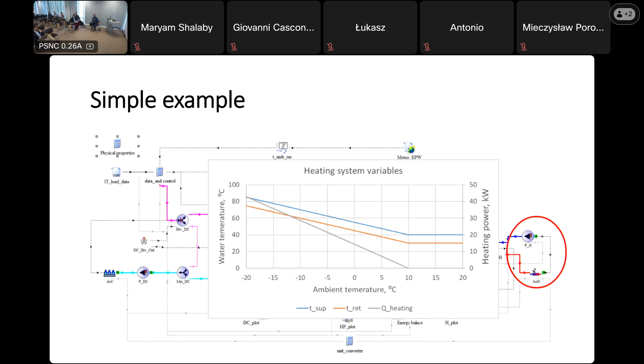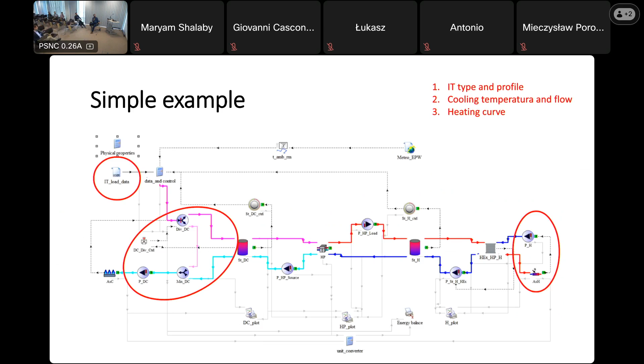Then the simple task was to find how the IT type and IT profile influence the performance indicators, how the cooling temperature and flow influence these performance indicators, and how the heating curve, so the building characteristics, also influences them. The IT profile we define here. The temperature and flow in the cooling system we define here. The heating curve is defined here.